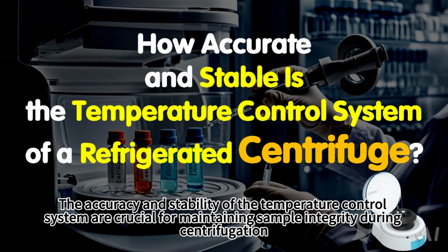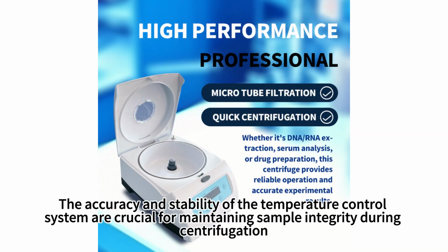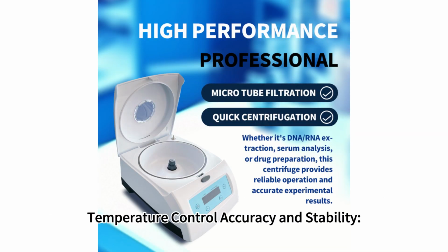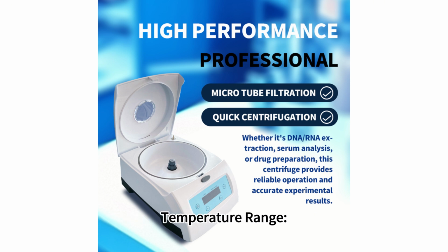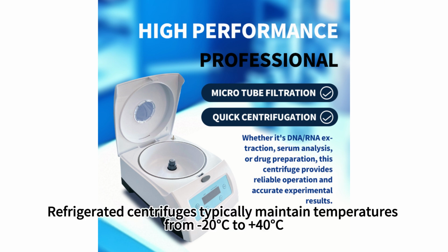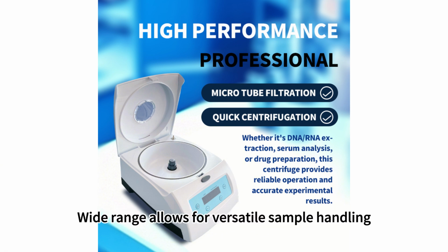The accuracy and stability of the temperature control system are crucial for maintaining sample integrity during centrifugation. Temperature control accuracy and stability, temperature range, capability. Refrigerated centrifuges typically maintain temperatures from -20 degrees C to +40 degrees C. Importance: a wide range allows for versatile sample handling.